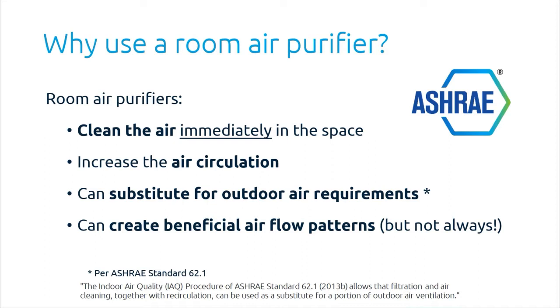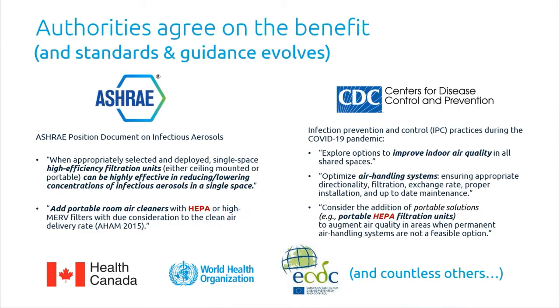It's immediately in that space where you can put an air purifier that, even if your HVAC system is doing a decent job, it can still do more within that space. You're increasing your air circulation, substituting for outdoor air requirements, and that's straight from ASHRAE. ASHRAE has calculations that say here's what you can do by adding air purifiers when you're not getting enough outdoor air in your building. And don't forget, we're targeting to get enough outdoor air, because that's what indoor air quality is all about at the top level. And it can create beneficial airflow patterns, which we'll talk about later.